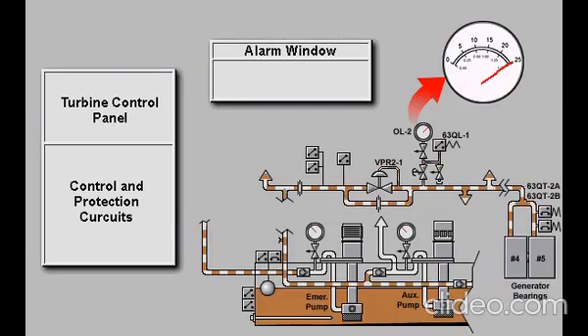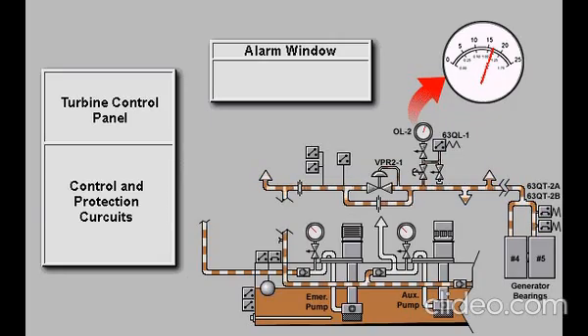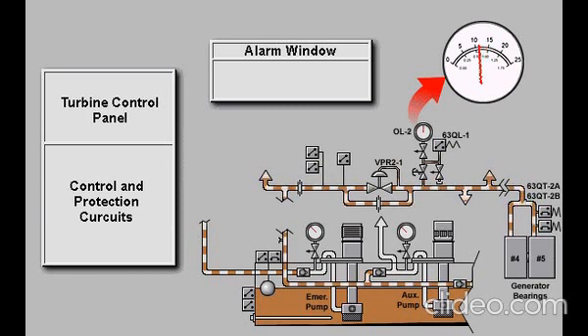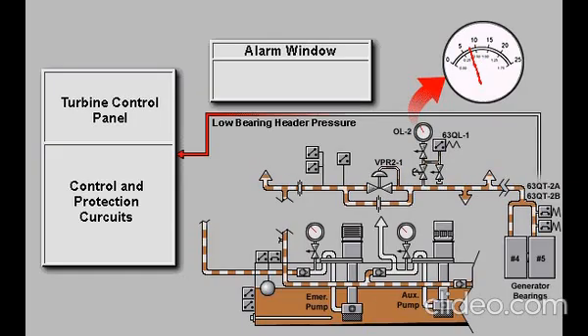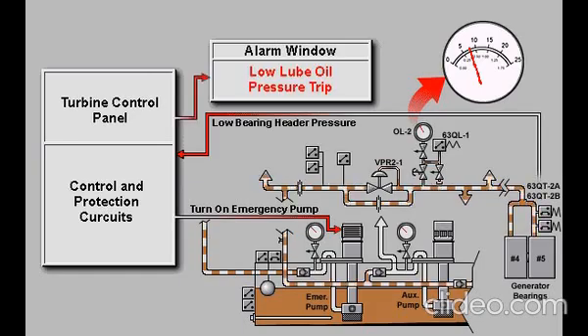During turbine operation, pressure trip switches 63QT-2A and 2B monitor the lube oil pressure in the bearing header at the back of the generator, farthest from the lube oil pumps. If pressure trip switches 63QT-2A and 2B sense a drop in lube oil pressure below 8 PSI, the emergency lube oil pump will start and the unit will trip on low lube oil pressure.